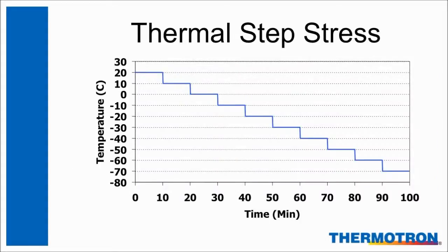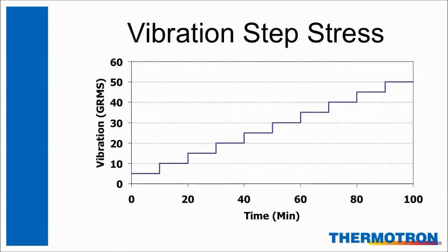Thermal step stressing is one way to perform HALT. A typical test begins at ambient temperature and will increase or decrease in 10 degrees C increments every 10 minutes. This is continued until there is a failure or the temperature reaches the fundamental limits of the technology used in the product. This could be the temperature at which a crystal stops working when getting cold, or the temperature that solder reflows when going hot. Basic HALT procedures also use step stressing for increasing vibration levels. The test starts at a low stress level, remains at each level for about 10 minutes, and then includes running the product's diagnostics. Stress levels are increased until a failure occurs. When a failure occurs during any of the temperature or vibration step stresses, the operator should stop the test, identify where the failure occurred, if possible temporarily fix the failure, and then continue increasing the stress.